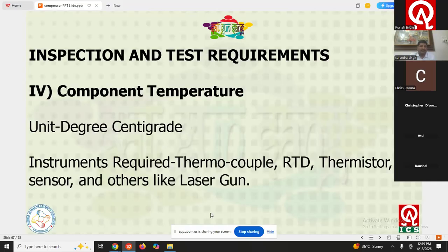If we are going to check the component temperature, the unit shall be the degree centigrade. Instruments required to check this component temperature are thermocouple, RTD, thermistor, IR sensor, and others like laser guns. Nowadays, the laser gun has come into the picture in the industry, so you can check the temperature through this laser gun.